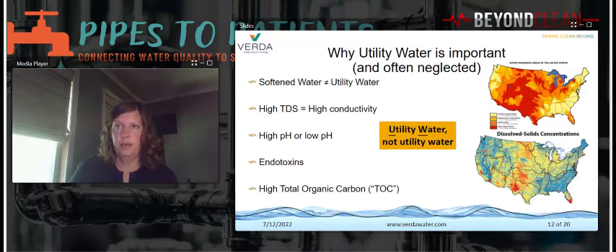Why utility water is often neglected is that there's an assumption that utility water is the same as facility water. If your facility's in a region that's colored yellow on the map or light orange, then maybe you think the water hardness is not very hard, it's low, so we're okay. However, just as we've seen, water hardness is just one aspect of what defines acceptable USP utility water. pH, conductivity, chlorides, bacteria, and endotoxin levels also need to be verified.